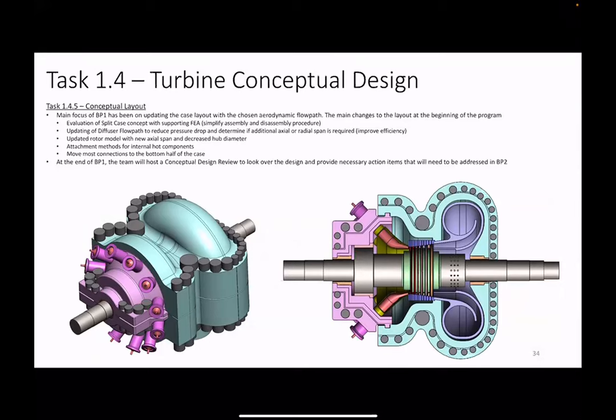Continuing on, we are also updating the case design of the turbine. The main thing to note is that we are going with a horizontally split body with split bolts. This type of construction allows for easy disassembly and maintenance of the rotor. If there's a damaged blade or a damaged combustor can, the top halves of the casings can be removed and the entire rotor lifted out. Otherwise, you'd have to remove the entire case, rotate it, and then remove the rotor. So for assembly and maintenance considerations, we wanted a horizontally split case.